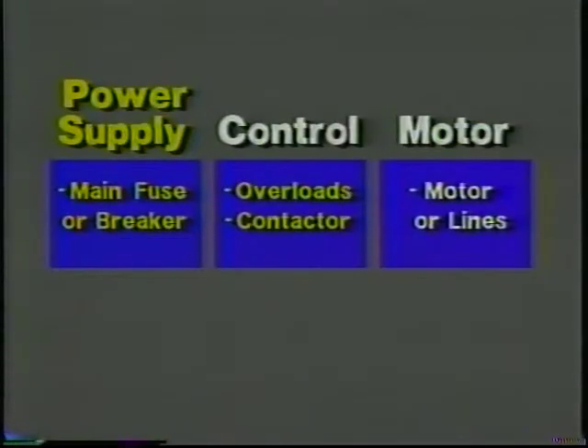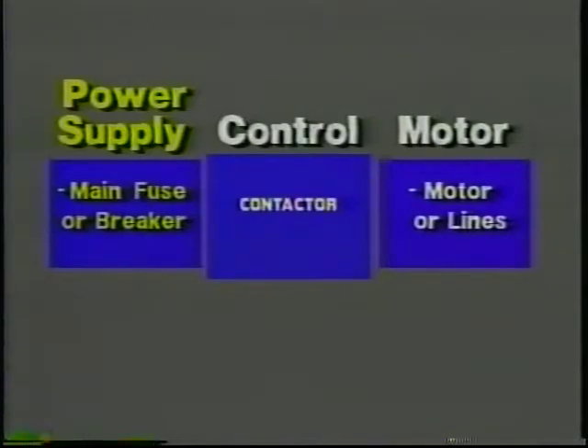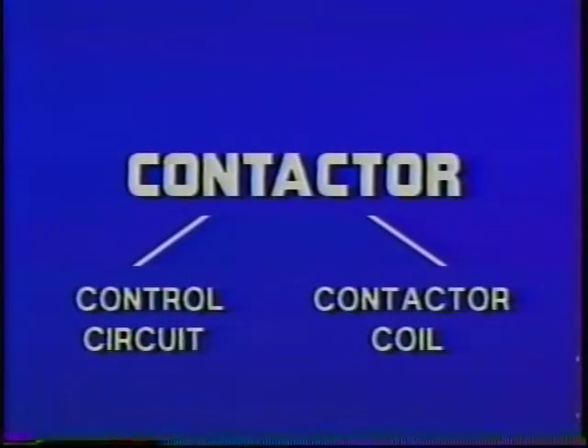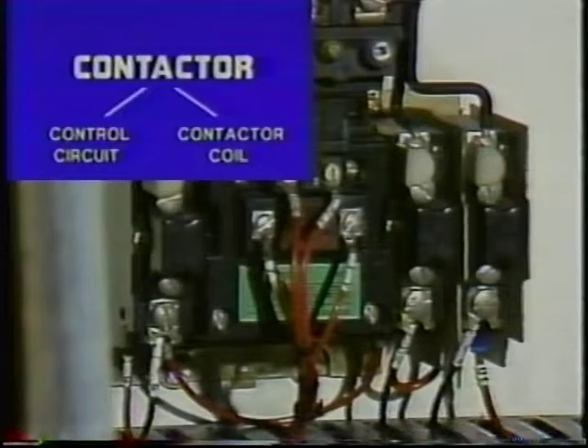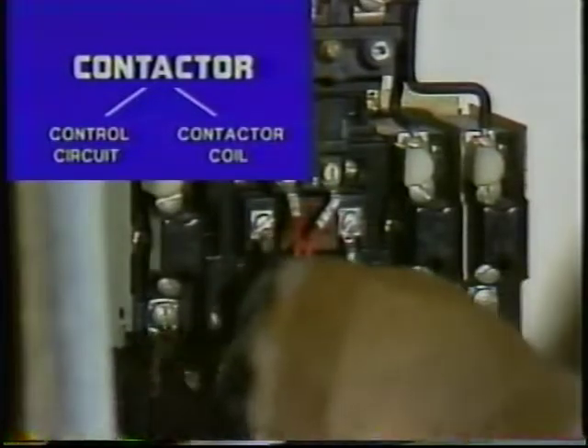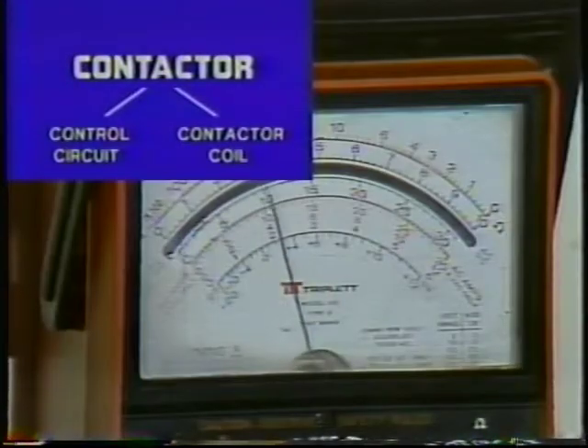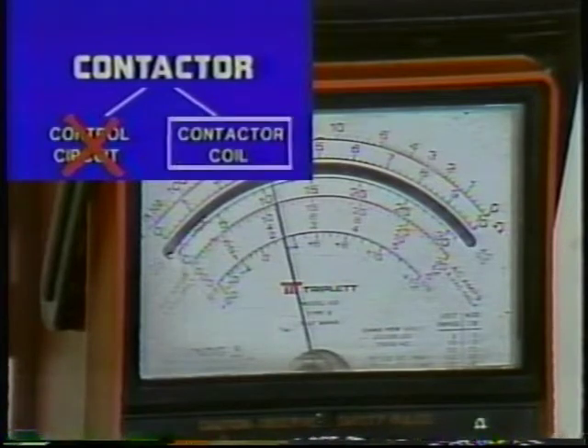But let's suppose for a minute that the problem was not an open in the motor. Suppose the contactor did not pull in. How would you continue troubleshooting the system? Well, the probable causes for a contactor not pulling in are either a problem in the control circuit or a bad coil in the contactor. To eliminate one or the other, take a test reading at the contactor coil. Normal control voltage eliminates the control circuit. Since voltage is reaching the coil, the coil itself must be bad.